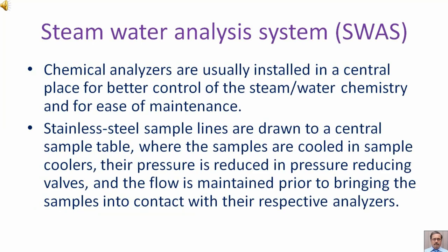Chemical analyzers are usually installed in a central place for better control of the steam/water chemistry and for ease of maintenance. Stainless steel sample lines are drawn to a central sample table where the samples are cooled in sample coolers.